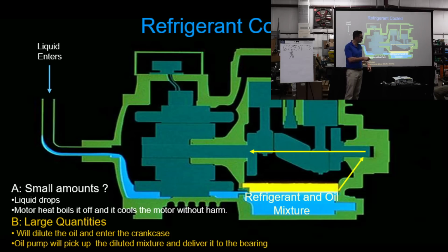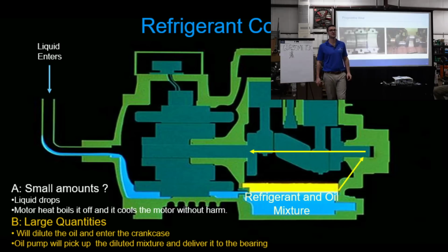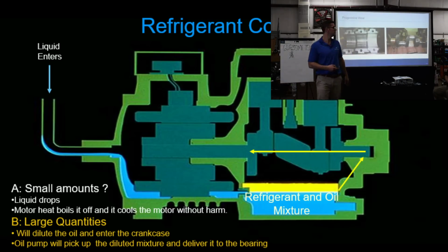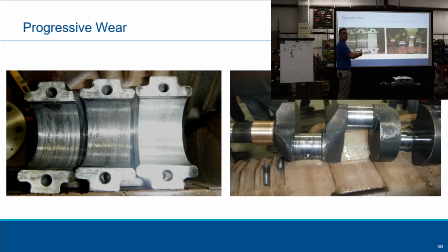This oil pump will suck it up because we drill holes through our compressors onto our oil pump. It sucks up the oil, but if it's sucking up refrigerant as well, it starts to wash out all the bearings. It's something we call progressive wear. As you can see, the bearing is not as bad here. You look at the pump bearing, it looks probably perfect because that's where oil is. But by the time it gets to the last bearing, it's failed.